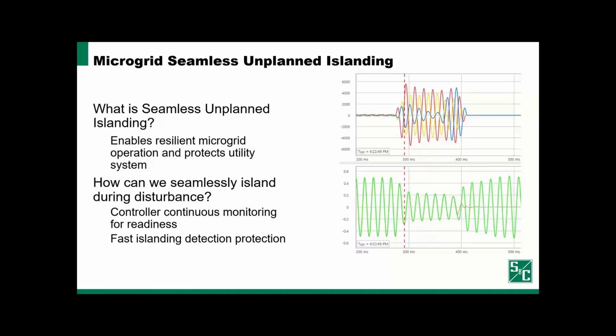This is an approach that we've used successfully in the past. You can see some oscillography. This is from an actual event at one of the microgrids that I contributed to the design of and commissioning of. On the top, you see fault current here, and you can see there's very clearly a fault occurring on the power system right around this dashed red line. The fault persists for about 100 milliseconds, and then it's clear. And you see a lot more here down on the voltage plot on the bottom.